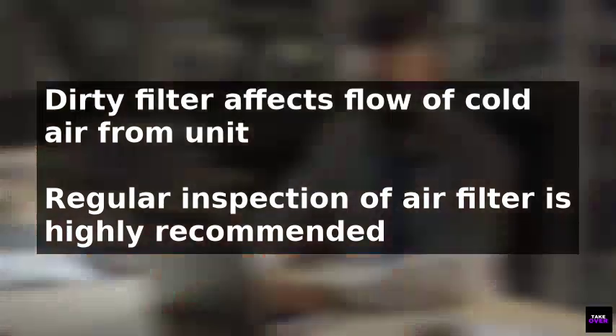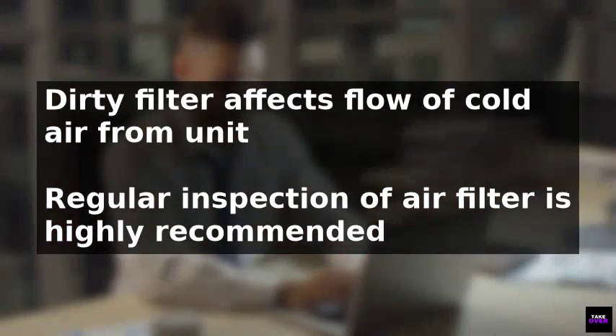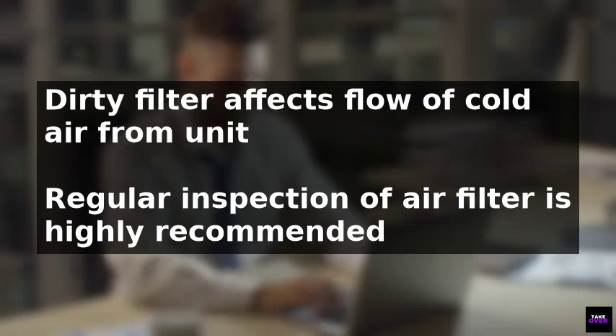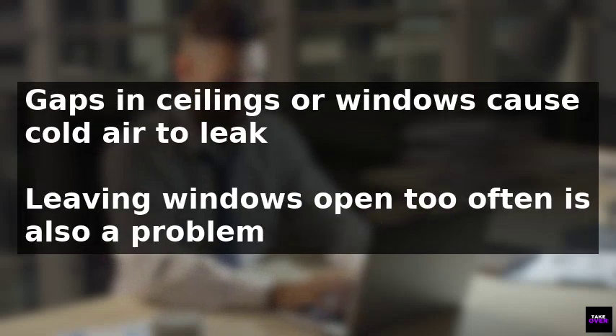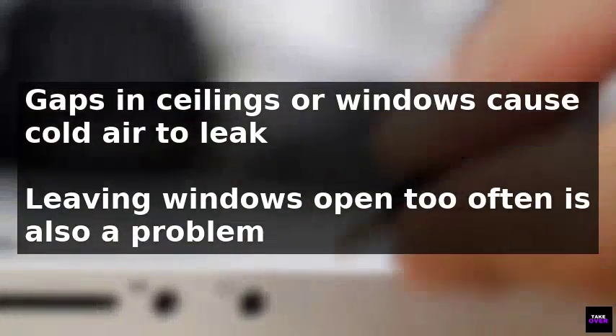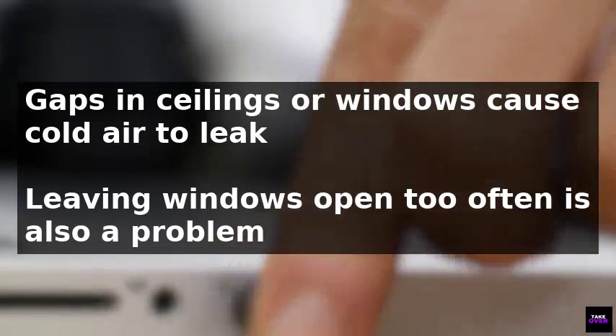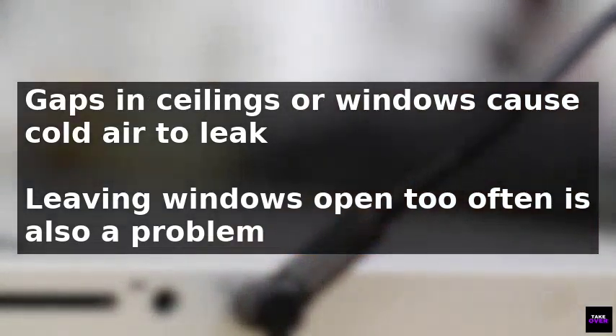A dirty filter can also affect the flow of cold air, so it is recommended to inspect the unit's air filter regularly, at least once a week, and clean it if necessary. Furthermore, gaps in ceilings or windows can cause cold air to leak out and hot air to enter. So it is vital to inspect walls and ceilings to identify any gaps and seal them.